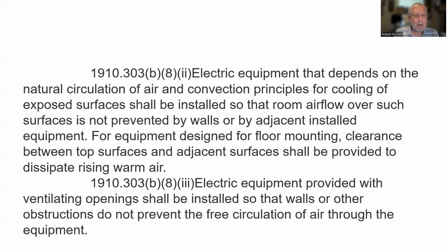Electric equipment that depends on the natural circulation of air and convection principles for cooling of exposed surfaces shall be installed so that room airflow over such surfaces is not prevented by walls or by adjacent installed equipment. For equipment designed for floor mounting, clearances between top surfaces and adjacent surfaces shall be provided to dissipate rising warm air. So they're talking about electrical boxes that get hot inside, and you want to get that dissipated. Some things have built-in fans to keep them cool. So you want to make sure you have clearance all around it, and you want to keep the top surface clear so that it'll dissipate the heat inside.